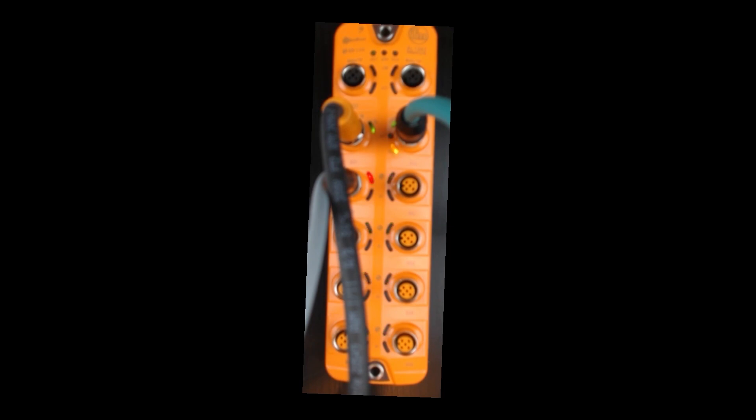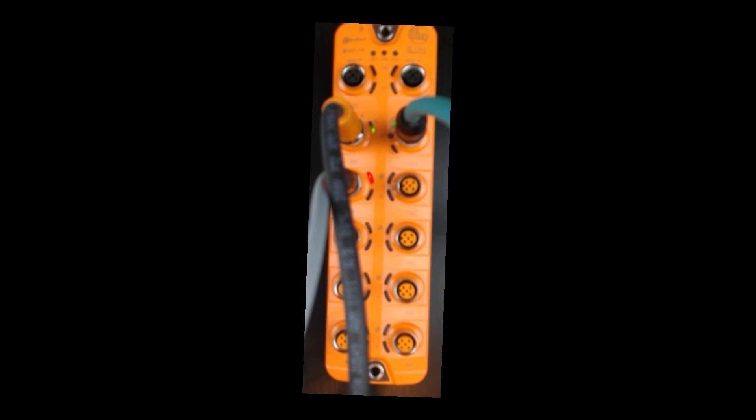let's take a look at what we see on our IFM master. So if you take a look at our IFM master, and I'm actually looking at the top-down view of our IFM IO-Link master, you can see the gray cable there connected to the first IO-Link device port, port one, and you can see that its connection is blinking red at about two hertz or so, indicating that the device that's connected is not permissible.